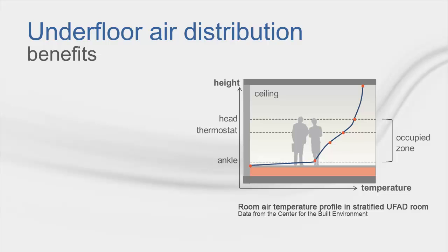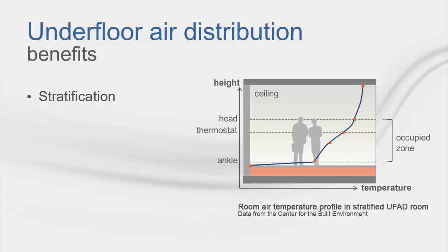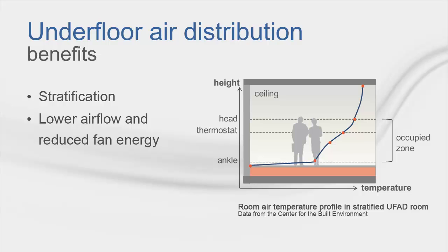So, what are some of the potential benefits of this system type? As you can see in the figure, temperature stratification in the conditioned space will result in higher temperatures at the ceiling, typically higher than the room thermostat setpoint, which will change the heat transfer dynamics in a room and between floors. However, this system only needs to condition a portion of the space, thus lowering airflow and reducing fan energy.